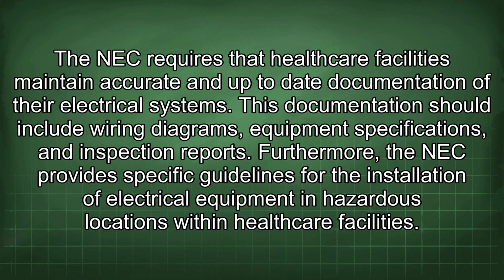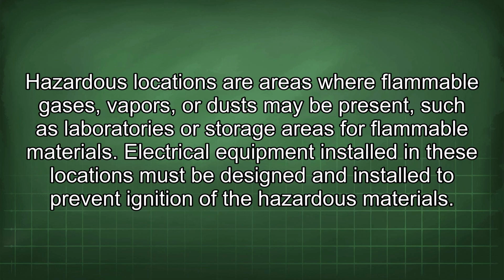This documentation should include wiring diagrams, equipment specifications, and inspection reports. Furthermore, the NEC provides specific guidelines for the installation of electrical equipment in hazardous locations within healthcare facilities. Hazardous locations are areas where flammable gases, vapors, or dust may be present, such as laboratories or storage areas for flammable materials. Electrical equipment installed in these locations must be designed and installed to prevent ignition of the hazardous materials.